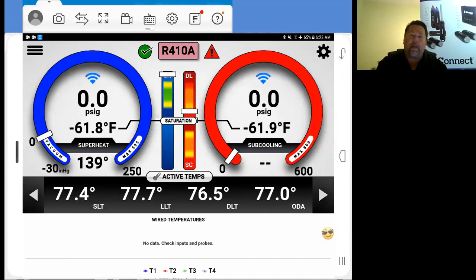If you go right above the coil, number one, the air is going to be very, very cold. That's not the real product that you're giving to the customer. And also, it's going to be saturated. You have very, very high humidity. Get it out, go ahead and do some air mixing. If you want to put them in the ductwork, go 10 or 12 feet down the line. Let it mix up with some air. That'll give you your best result.